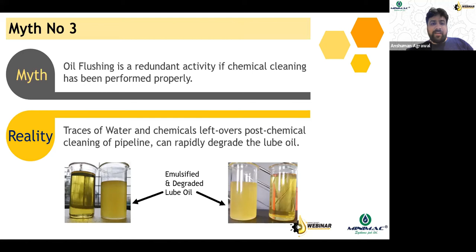In fact, we have seen multiple cases at projects where fresh oil was charged in the lubrication system, and as soon as it was charged, it got emulsified. So you can see the pictures below that emulsification happened very fast, and because of this, they could not actually start the project. The reason was the traces of water which were present in the entire system because of the chemical cleaning activity. They started mixing up with the charged lubricant and contaminated it immediately. So that's the reason why you need to perform a proper flushing whenever you perform the chemical cleaning activity.